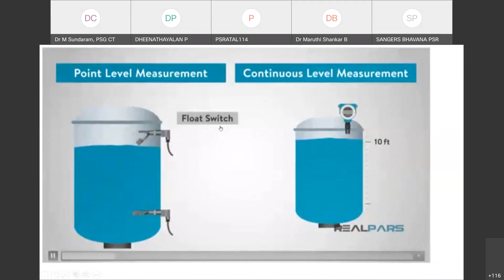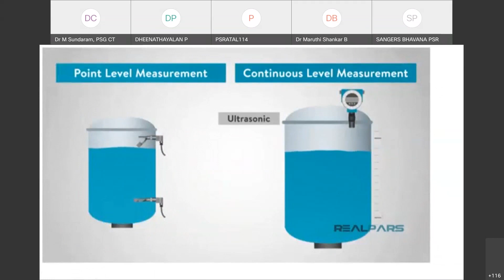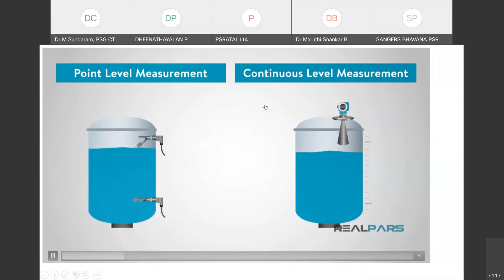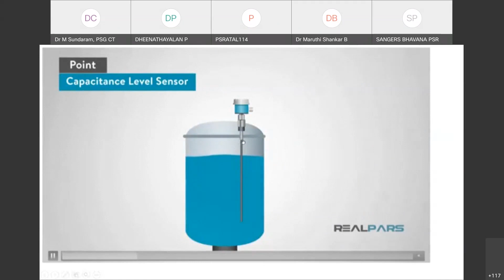Capacitance, optical, conductivity, vibrating tuning fork, float switch. So these are the different sensor types being used for level measurement. Ultrasonic and radar both are used for continuous measurement. Mostly ultrasonic are used. Radars are used in big silos, particularly in very higher end mechanisms like chemical industries, fertilizer based.